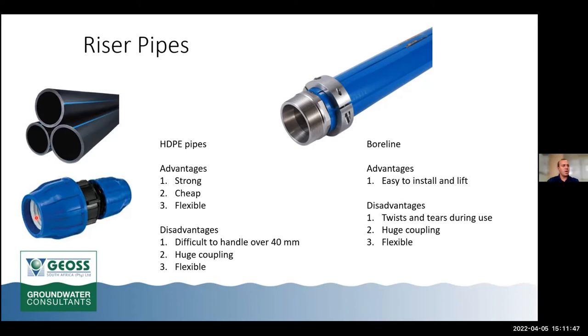Next, boreline — a very controversial type of riser pipe. The only advantage is that it's easy to install and to lift, but there are several disadvantages. First is wear and tear: as soon as you start using it, the motion of the pump in the borehole starts twisting the pipe, and we often see tears and cuts after short durations of use. It also has huge stainless steel couplings that often get caught if not removed correctly. And like the others, it's flexible — should the pump get stuck, you cannot push down on it.